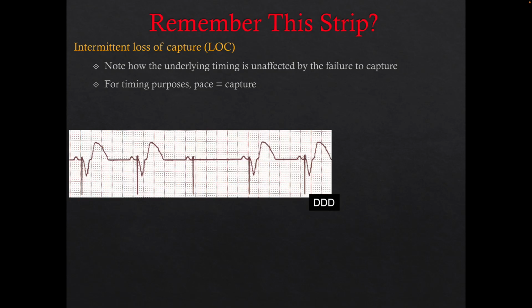The reason why we call this loss of capture is because if you measured this with calipers or what have you, you can see the output trying to be output from the pacer is at the same interval, but it doesn't capture. So that could be a huge problem if it keeps happening. And it's something that you can adjust in both this device and this device. You would be setting the MA on this. Okay. All right. Do you know what might cause this?